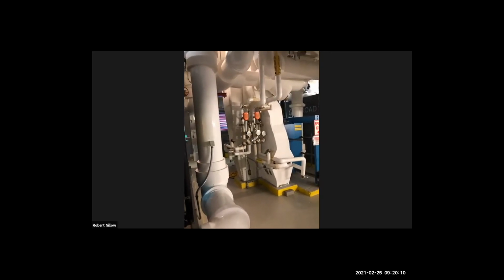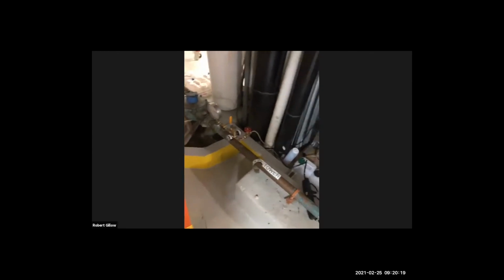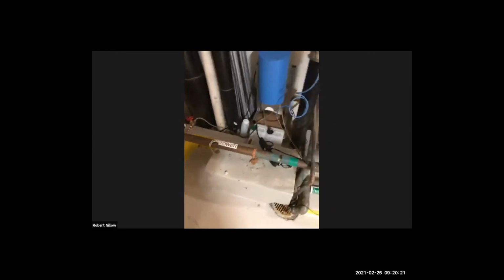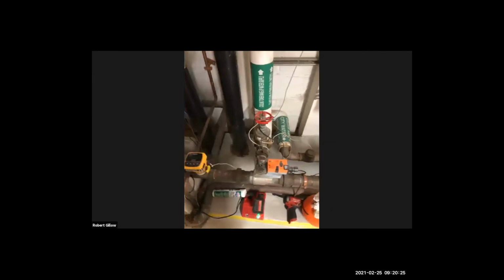All right. So Bob, if you turn back to the blending valve. So Mike spoke about phosphates and controlling phosphates. So very early on, when we started the Solaire, we were getting orthophosphate deposition on the heat exchangers.